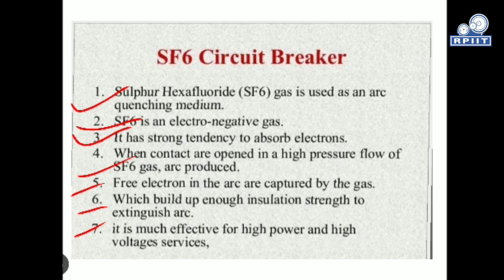Next, it builds up enough insulation strength to extinguish the arc. So it behaves like an insulating gas as well, and directly extinguishes the arc. It is more effective for high power and high voltage services, such as long transmission lines or substations of 220 kV and 132 kV, where we utilize SF6 circuit breakers. Nowadays SF6 and vacuum circuit breakers are widely used for this reason.